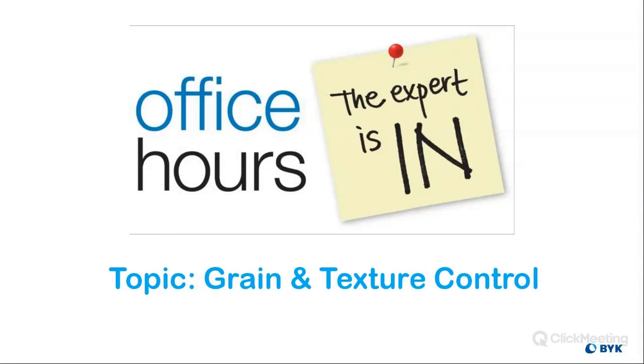No moving the device around to do the different types of measurements. It's just position it over your surface, one click of the button, and you get color, gloss, and graininess. So yeah, 60-degree gloss. And the graininess, the topography, and the reflectivity measurements, those pictures are analyzed in various ways.